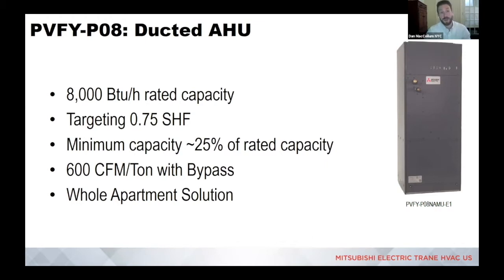And part of the way that we're getting that sensible heat factor ratio down so low is having an internal bypass circuit that allows, inside the indoor unit, for us to introduce some return air into the airstream before we bring it into the supply ductwork. It might seem counterintuitive off the bat, but in our experience, these systems are able to cool down a passive house space so quickly that you lose the dehumidification benefits of a DX system. If we're able to temper those leaving air temps a little bit and make them more moderate, it'll allow the system to run in cooling for an extended period of time, not immediately cool down the space and deactivate the DX coil, but bring some moisture out of the air for a more extended period of time.